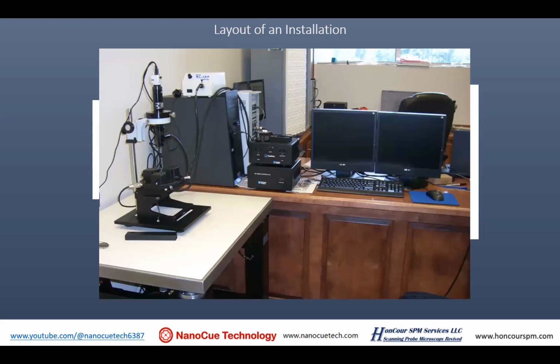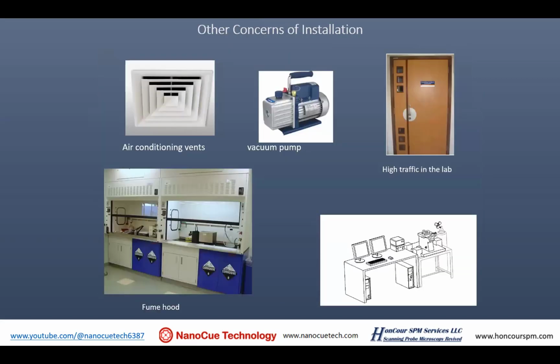This is a picture of a typical operation. I like to have an L-shaped installation. Basically, you sit in one location and can have your fingers on the switches at the same time. You can operate the instrument, and you have the instrument surrounding you. That's a good arrangement. Try to avoid these locations: doors, vacuum pumps, vents, and fume hoods, which have a big draft of noise.